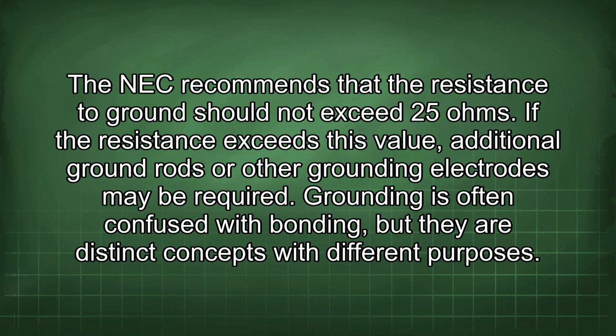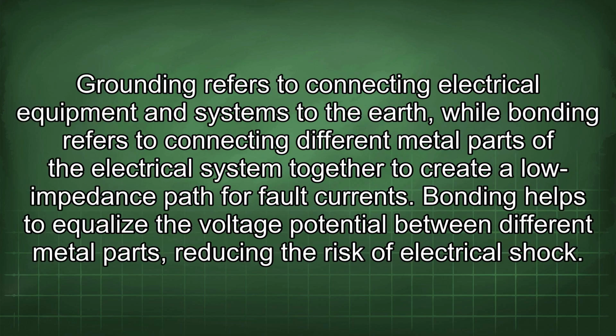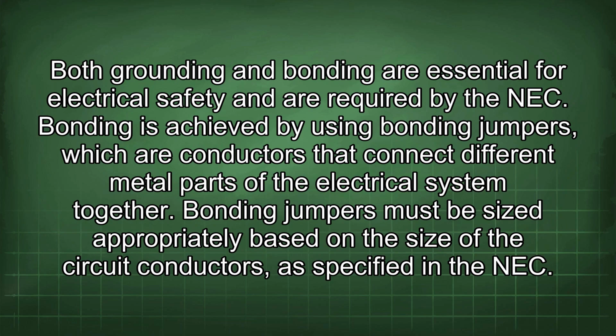Grounding is often confused with bonding, but they are distinct concepts with different purposes. Grounding refers to connecting electrical equipment and systems to the earth, while bonding refers to connecting different metal parts of the electrical system together to create a low impedance path for fault currents. Bonding helps to equalize the voltage potential between different metal parts, reducing the risk of electrical shock. Both grounding and bonding are essential for electrical safety and are required by the NEC.